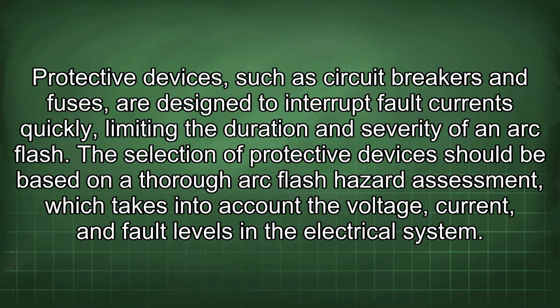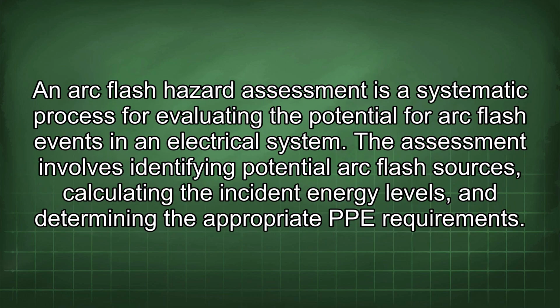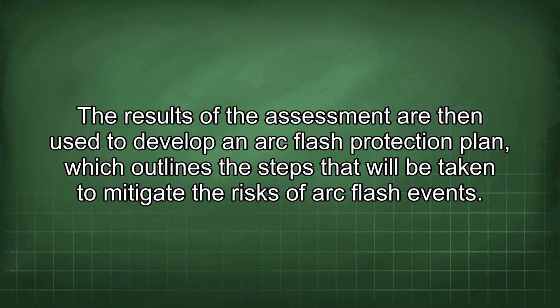Protective devices, such as circuit breakers and fuses, are designed to interrupt fault currents quickly, limiting the duration and severity of an arc flash. The selection of protective devices should be based on a thorough arc flash hazard assessment, which takes into account the voltage, current, and fault levels in the electrical system. An arc flash hazard assessment is a systematic process for evaluating the potential for arc flash events in an electrical system. The assessment involves identifying potential arc flash sources, calculating the incident energy levels, and determining the appropriate PPE requirements. The results of the assessment are then used to develop an arc flash protection plan, which outlines the steps that will be taken to mitigate the risks of arc flash events.